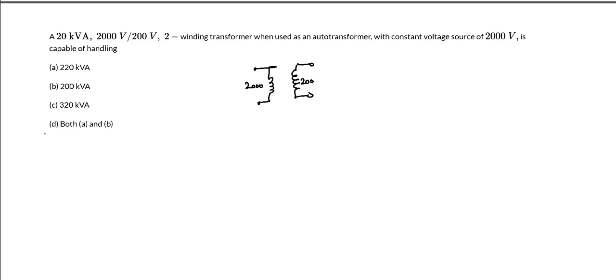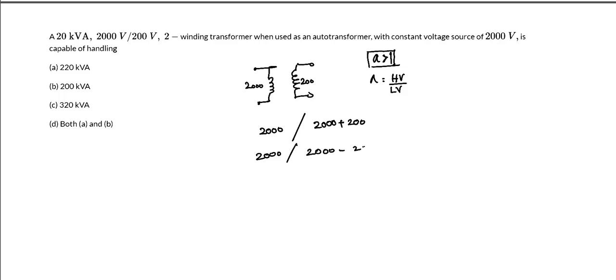If I convert it to an auto transformer, he does not mention additive polarity or subtractive polarity. But we know that the turns ratio A of the auto transformer must be greater than 1, or A equals high voltage by low voltage. If I consider 2000 volts as the constant voltage source, what are the possibilities? One is 2000 plus 200, additive polarity. Another is 2000 by 2000 minus 200. So this is equivalent to 2000 divided by 2200, and this is equivalent to 2000 by 1800.